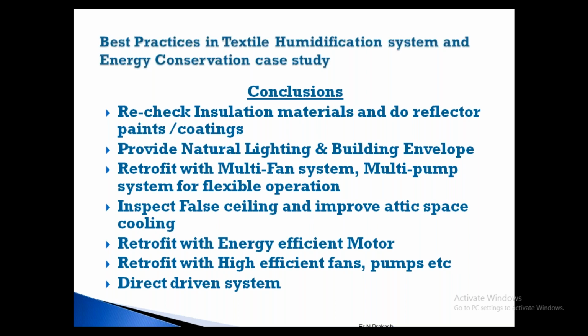Inspect the false ceiling and improve the attic space cooling. Attic space cooling is very important. After the false ceiling, there is a gap from the roof. If you do better cooling in that place, the solar heat radiation from the sun reduces inside your factory premises, so you will be able to maintain a better dry bulb temperature and RH. Retrofit with energy efficient motors. Of course, everybody knows this. Almost everybody is trying to replace motors with energy efficient motors.